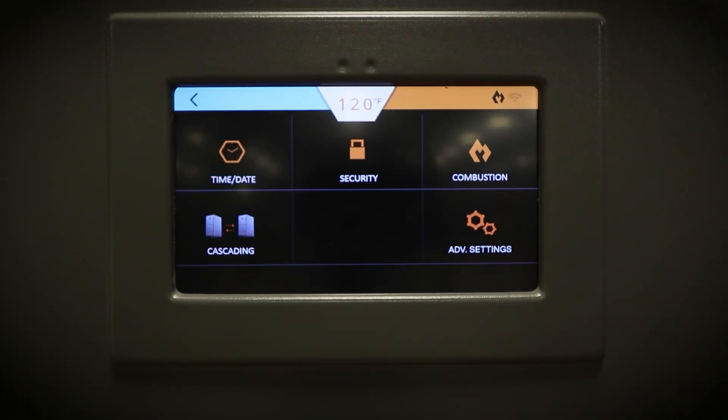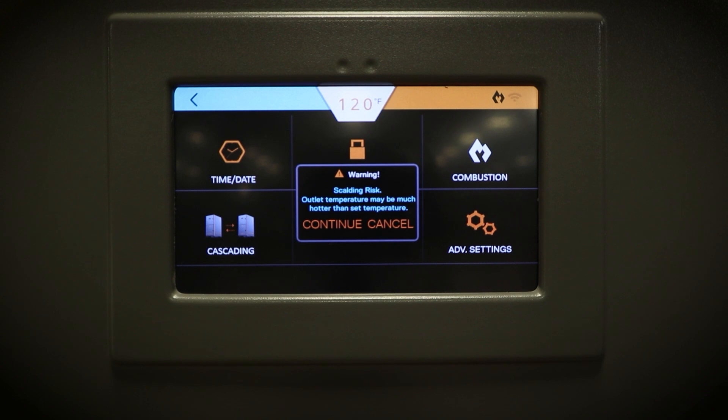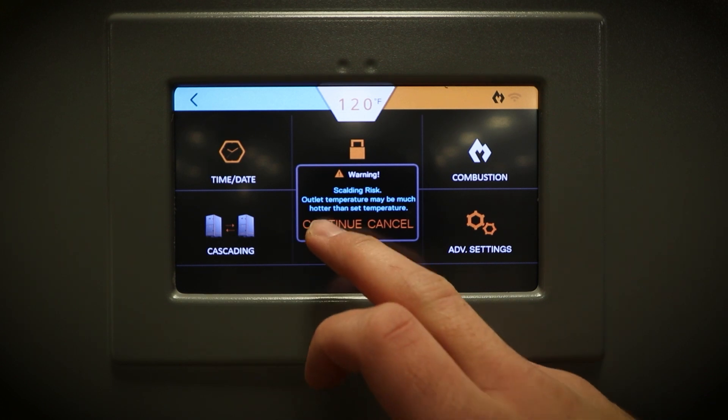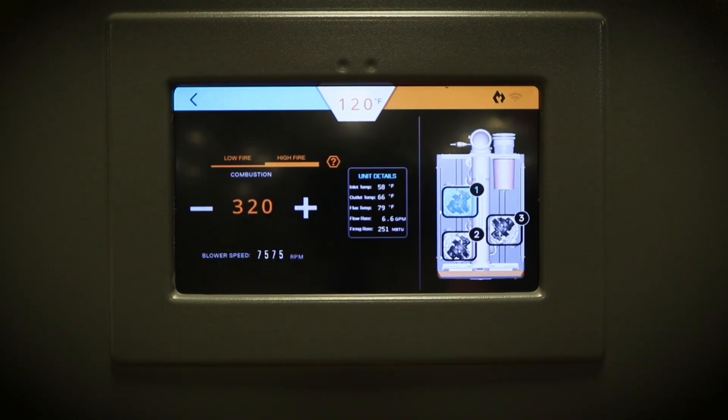To enter combustion mode, the unit will need to operate at its maximum firing rate. We will achieve this by increasing the demand of the heat exchanger. Please do the following: Calculate the difference in temperature between the unit set point and the incoming water temperature. This is our temperature delta.